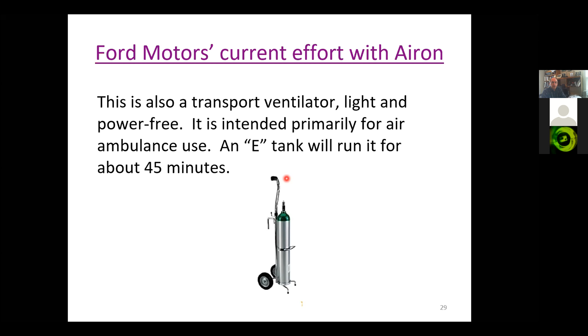Well, if you're asked to help, what are the engineering requirements of a piece of equipment that is life critical? It can't have point failures. At least the entire system into which it's integrated cannot have point failures. So you have to make sure that your instruction set to the skilled users who will be using this says you must have spare oxygen tanks, you must have an ambu bag there. You can't permit a failure of this ventilator all by itself to kill the patient. You have to have alarms. You have to have some fail-safe that notifies a skilled and trained operator. You have to have the protocols written. They have to be good.